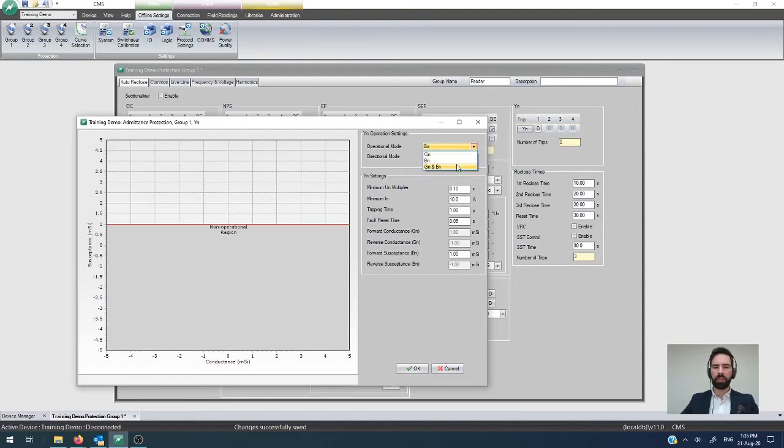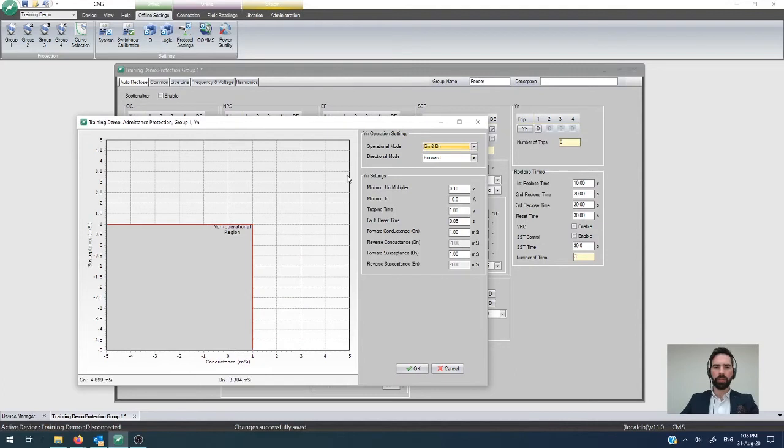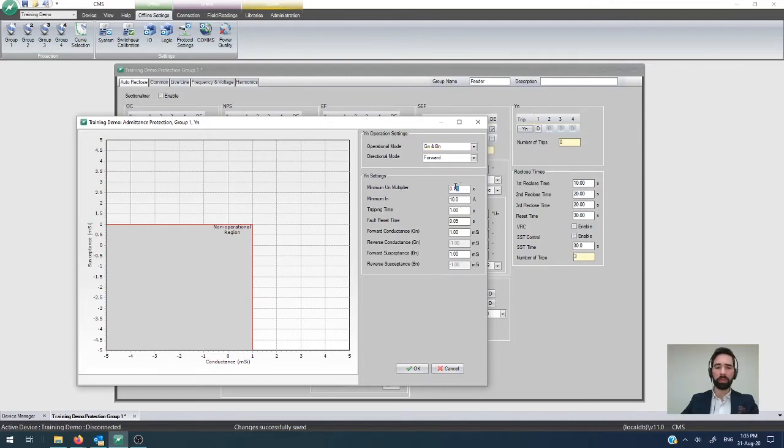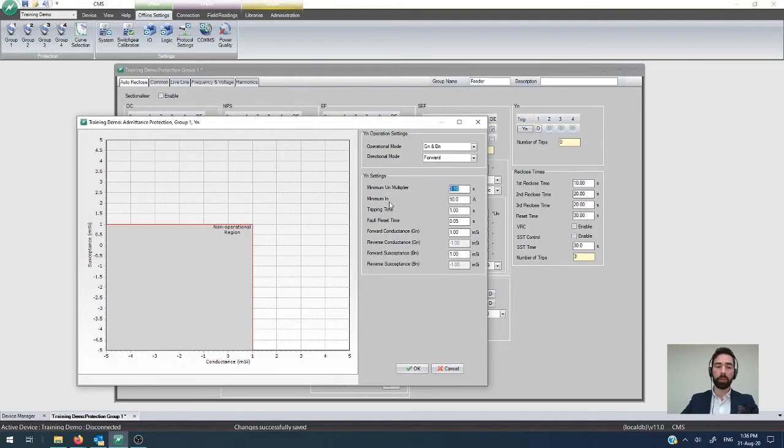If you are going to use this protection functionality then you can also stipulate what your minimum neutral voltage multiplier needs to be so that's the amount of neutral voltage displacement that has to be present before the element kicks in and also the minimum earth fault current that you need to see so that's neutral current there.